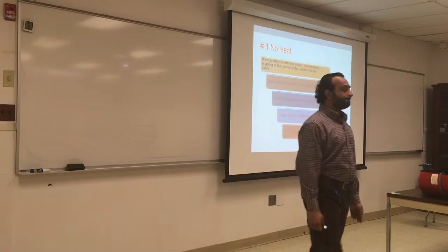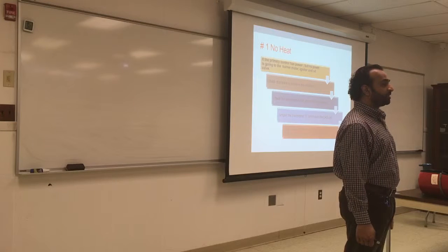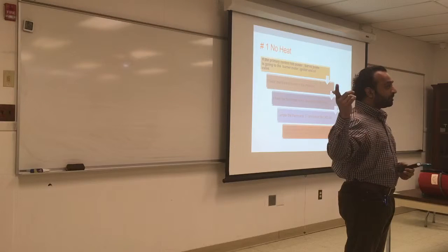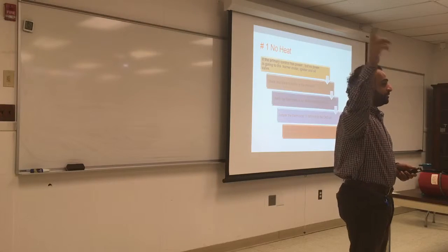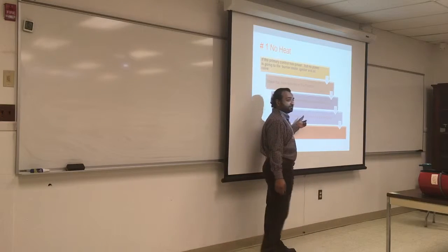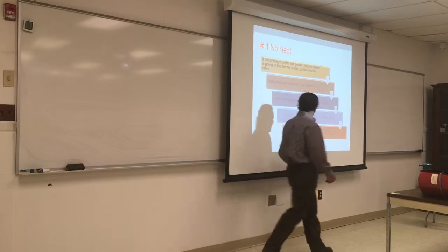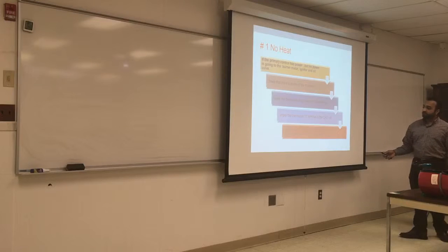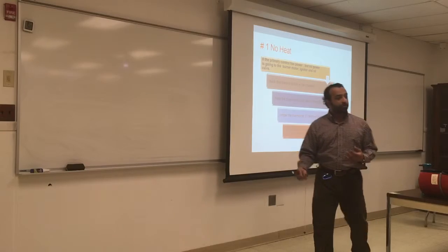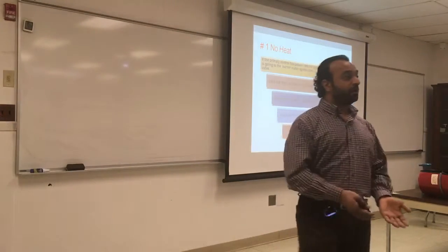Next step, check that the thermostat is set above the room temperature. It's above the room temperature. Okay, let's go and jump on the thermostat and see what happens. If it works, something is wrong with the thermostat or the wire from the thermostat all the way to the primary. So we jump it. And if it works, I mean, it's the thermostat. If not, you can go further. If the burner does not start, jump on the F-F terminal. If the burner starts, then the cad cell is bad. So it's going to be either the cad cell or the thermostat. If none of that works, the primary is faulty, something is wrong with it. Change the primary.